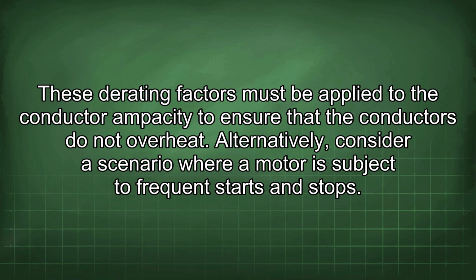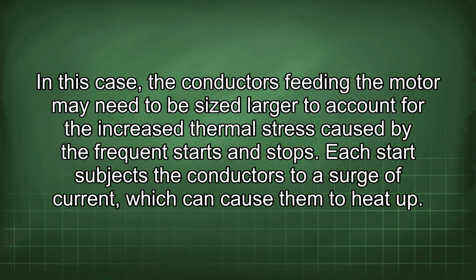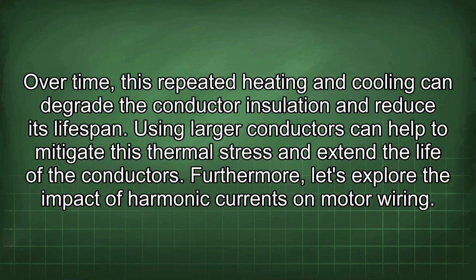Alternatively, consider a scenario where a motor is subject to frequent starts and stops. In this case, the conductors feeding the motor may need to be sized larger to account for the increased thermal stress caused by the frequent starts and stops. Each start subjects the conductors to a surge of current, which can cause them to heat up. Over time, this repeated heating and cooling can degrade the conductor insulation and reduce its lifespan. Using larger conductors can help to mitigate this thermal stress and extend the life of the conductors.